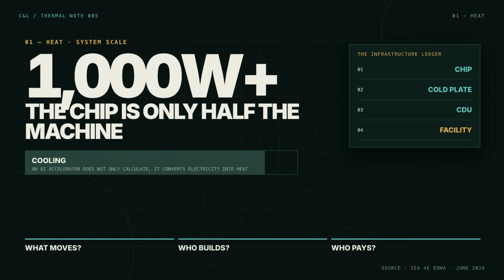Someone must move heat from silicon to a cold plate, from the rack to a cooling distribution unit, from the building to the outside environment, and sometimes into a useful heat network. Nvidia may make the headline chip. The cooling money is distributed across an entire thermal supply chain.